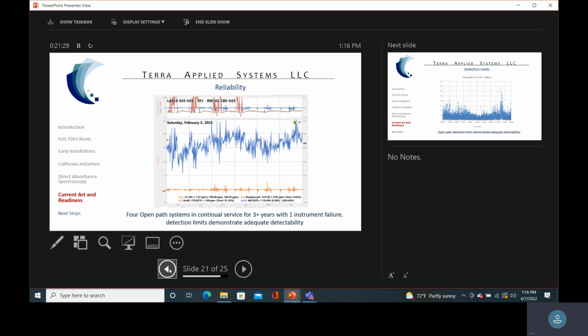Also measuring the water, 2 reasons. It's a check on the fit for the H2S measurement, and it's also a permanent gas in the atmosphere to verify it's in a reasonable range where it should be detected. So it's a real-time check gas. It's a co-detection.